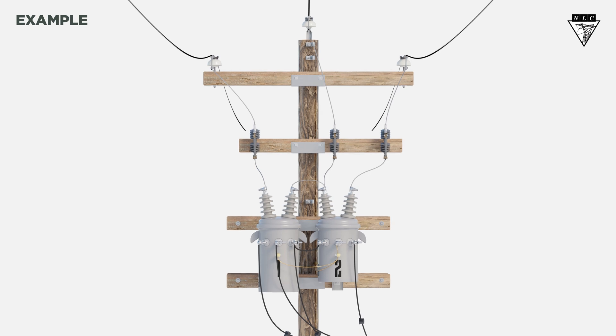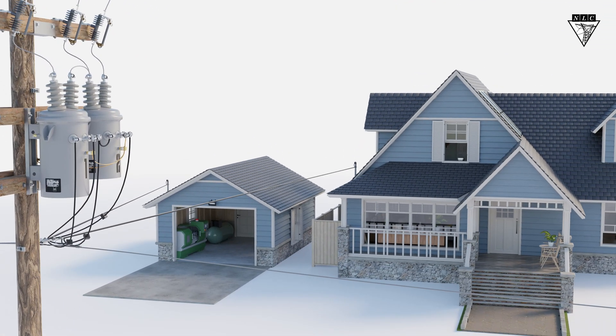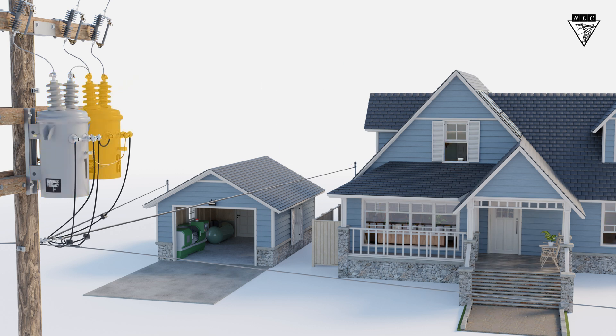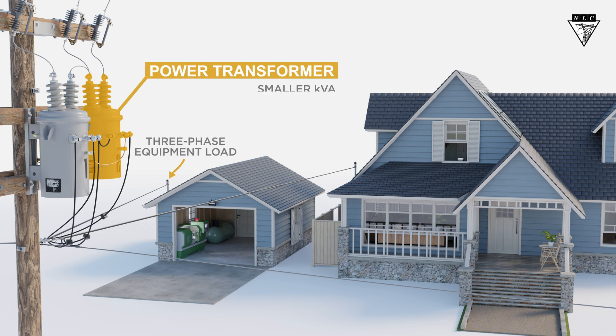Here's an example. If a customer requires a combination of three-phase and single-phase power, with the single-phase load prioritized over the three-phase load, an open bank may be used. In this case, one transformer will be larger in KVA so that it can handle the single-phase load and part of the three-phase load. We call it the lighting transformer because it supplies the bulk of the lighting load — in other words, it powers the lights. The smaller transformer is reserved and has a lesser KVA rating to help supply the third phase, or power leg. We call the smaller transformer the power transformer.